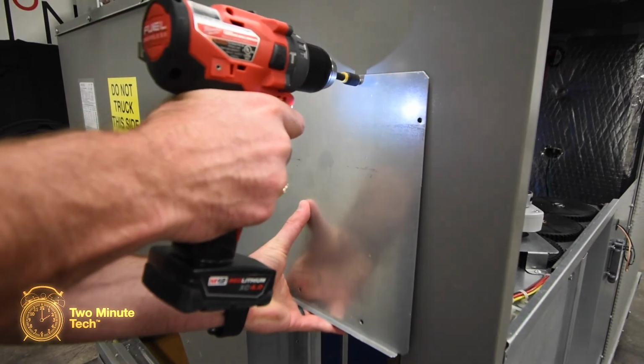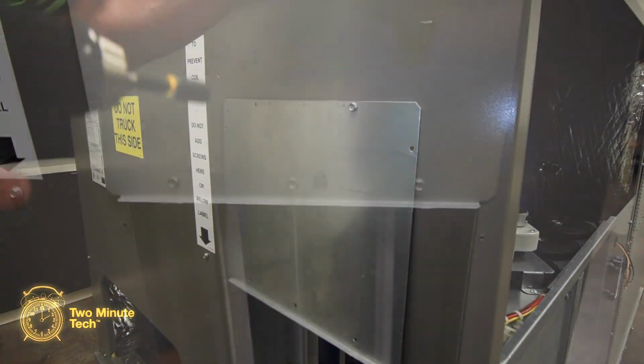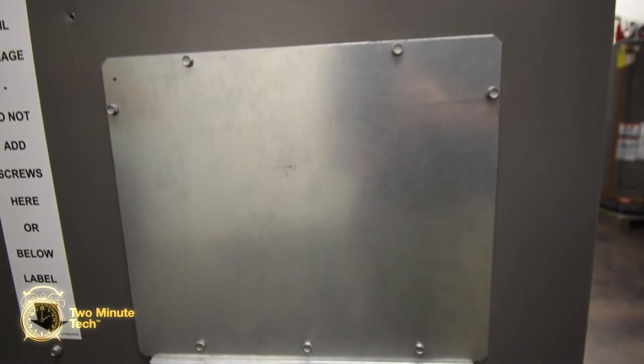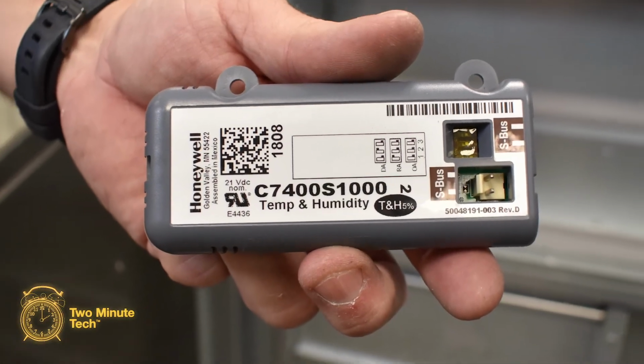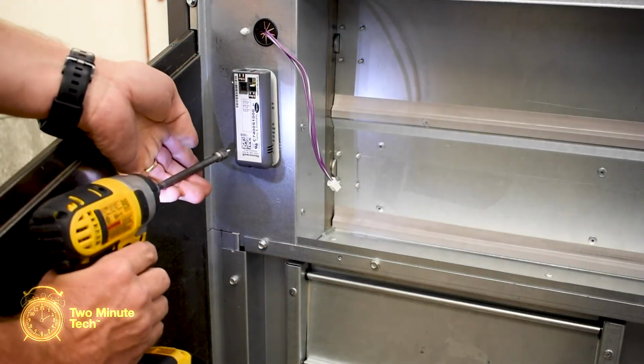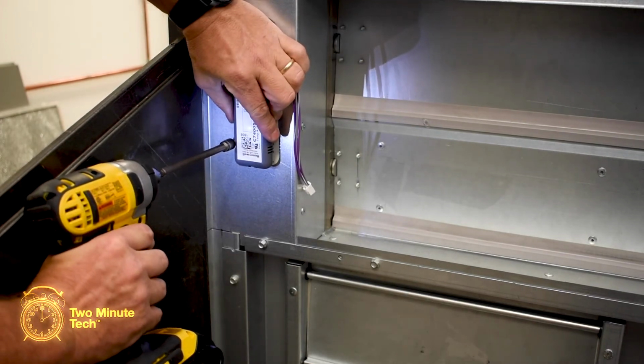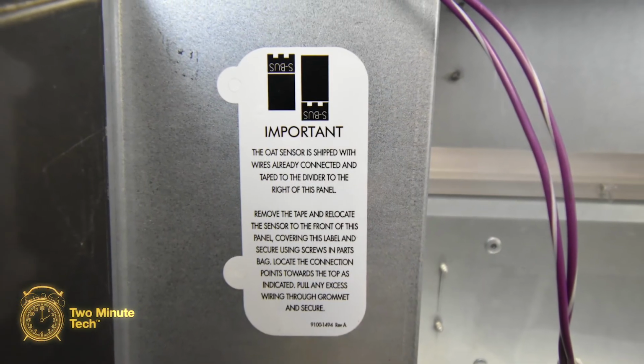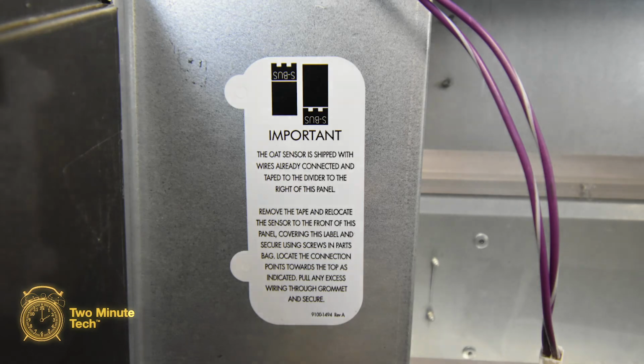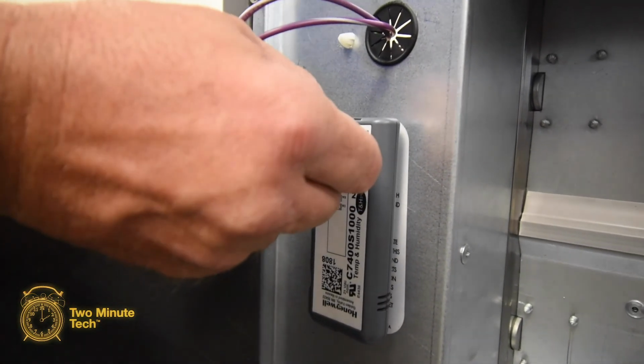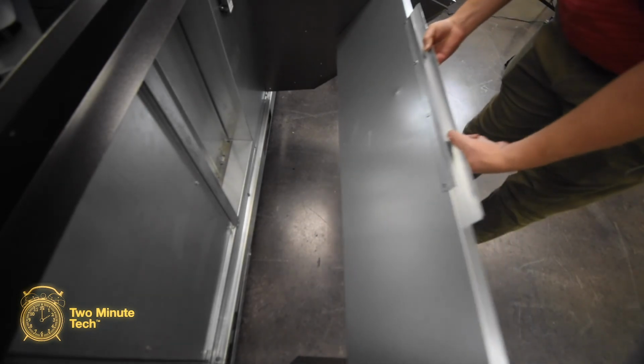Install the return air block-off plate over the top opening of the return access prior to the installation of the ductwork. Mount the outdoor air enthalpy sensor to the damper housing using the provided screws. A label indicates the correct location for the sensor. Connect the cable with the purple and white striped wire to the plug on the enthalpy sensor. Install the hood bottom panel between the 2 side panels using 3 screws on each side.